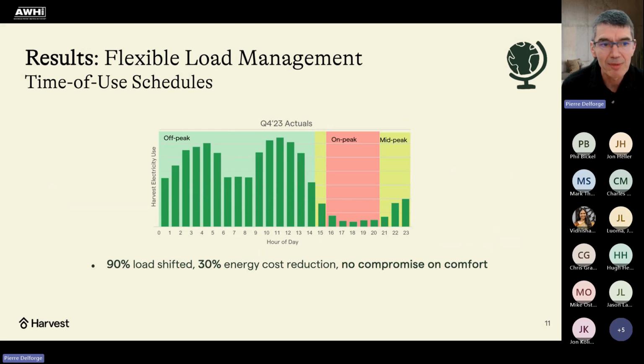The system was able to shift 90% of the load off peak, and importantly, without the need for people to curtail their heating temperature to preheat or pre-cool. It's basically no compromise of customer comfort—they get everything they want from the thermostat, while the thermal battery does the work in the background.